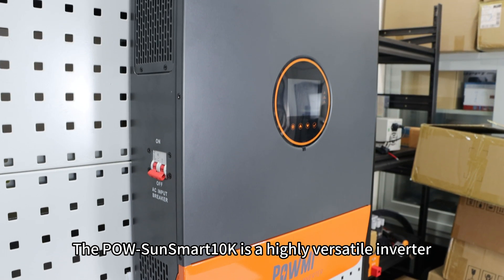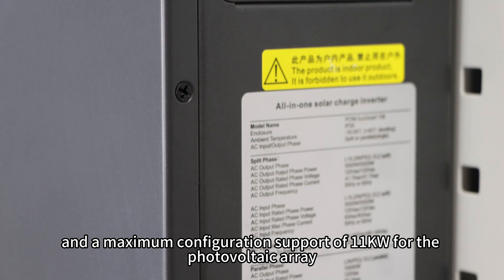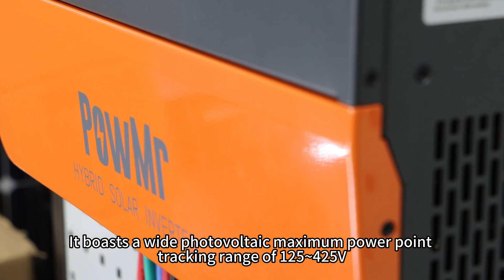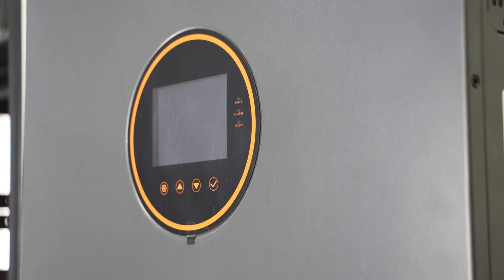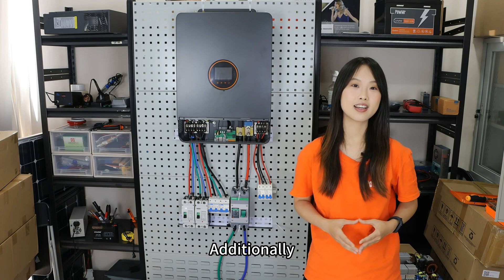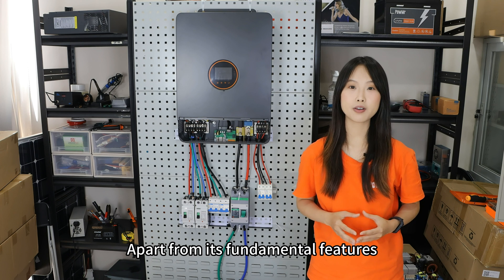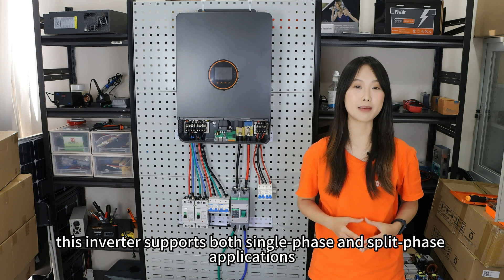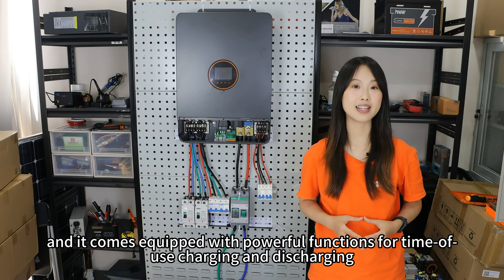The POW-SunSmart10K is a highly versatile inverter with a rated output power of 10kW and a maximum configuration support of 11kW for the photovoltaic array. It boasts a wide MPPT range of 125–425V, 2 MPP trackers, and a maximum current of 22A per channel. The charging module is capable of delivering a maximum charging current of 200A. This inverter supports both single-phase and split-phase applications and is equipped with a powerful time-of-use charging and discharging function.